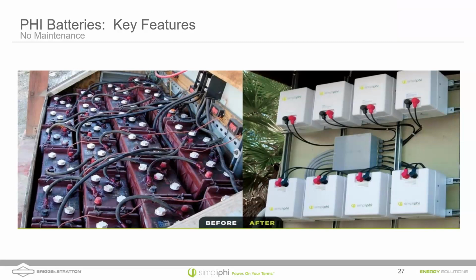So we would want to water the batteries and make sure that we keep the electrolyte filled up, potentially a specific gravity test. We would want to clean some of those terminals as well. And so it could be maintenance. And one of the things I've always seen is a lot of homeowners choose not to subscribe to any of your service plans or maintenance packages, which ultimately the homeowner forgets to water the batteries, and they end up with a damaged battery bank, and you're coming out to have to replace that lead acid. So in a lot of ways, being maintenance free can save some of the homeowners a lot of money.